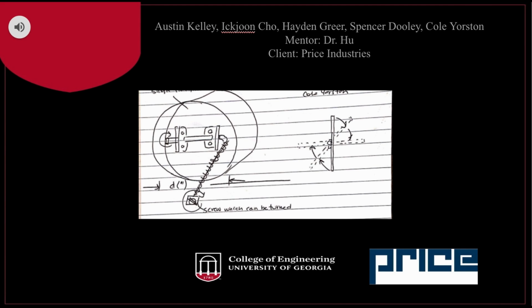Here we have design 2, which builds off of the original cable design but uses a single flap instead of a butterfly style of opening and closing. This damper would be operated by an elbow joint and a single rod which would sit behind the flap. This design had the potential to decrease manufacturing costs because it is a much more simple design than the original VCR8 EC damper. However, it was not chosen as our final solution due to the issue of the plate hitting the back wall of the plenum when being rotated to increase airflow.